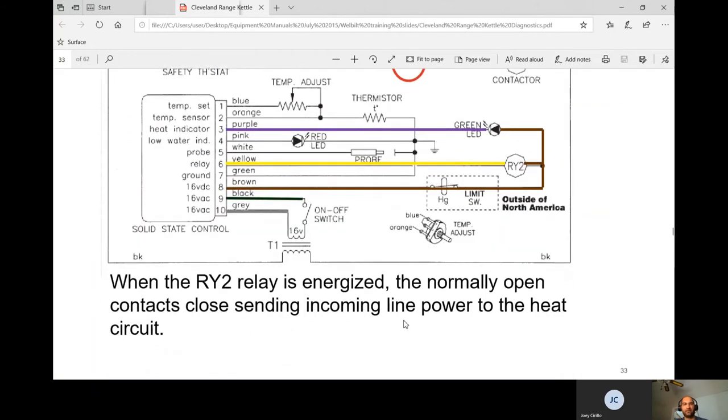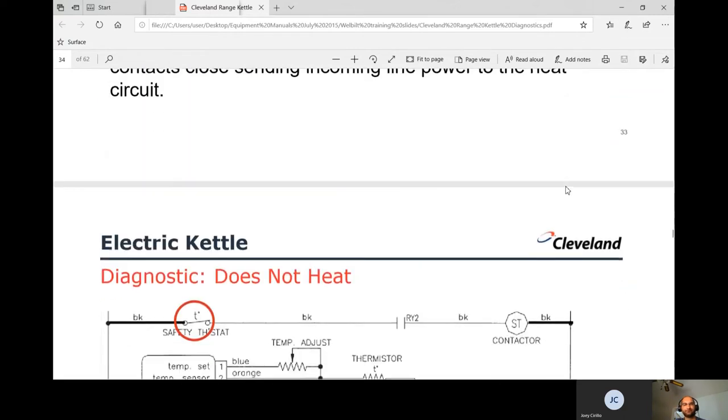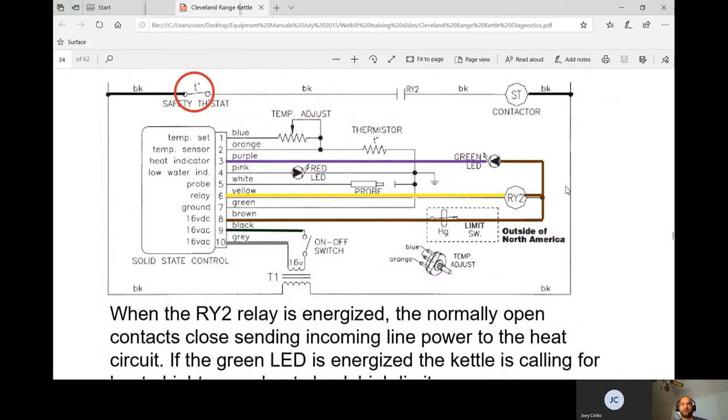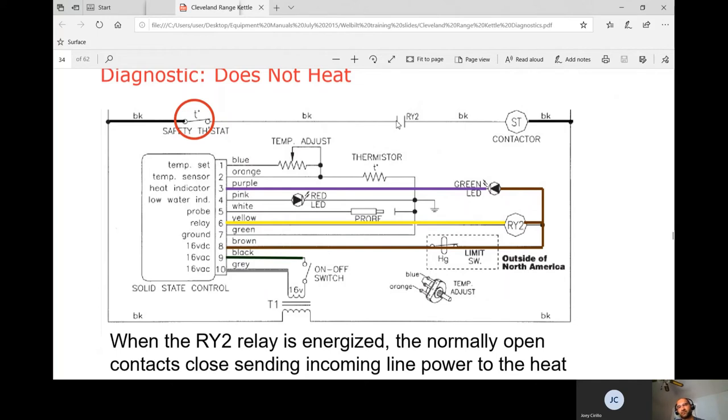When the RY2 relay is energized, it closes its contacts — if the high limit is good, those contacts close and the contactor coil gets power. If the RY2 relay is energized but you're not getting power into the relay, work backwards upstream and check the safety thermostat. Whenever the green light is on but you're not heating, the first thing to test is the safety thermostat. Use the schematic and the LEDs as diagnostic hints so you don't have to test every component.